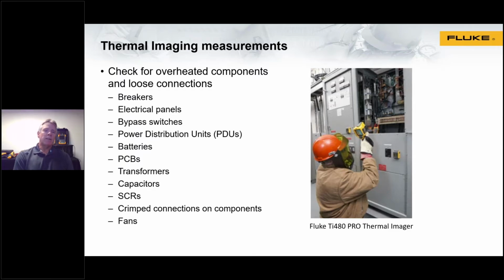There are a lot of different areas in a UPS system that you could check. I'm sure it's not an exhaustive list, but anywhere from the electrical panels to breakers, looking at switches, PDUs or power distribution units, batteries, battery connections, even printed circuit boards, transformers, really any component that might be critical to the operation of that UPS system.